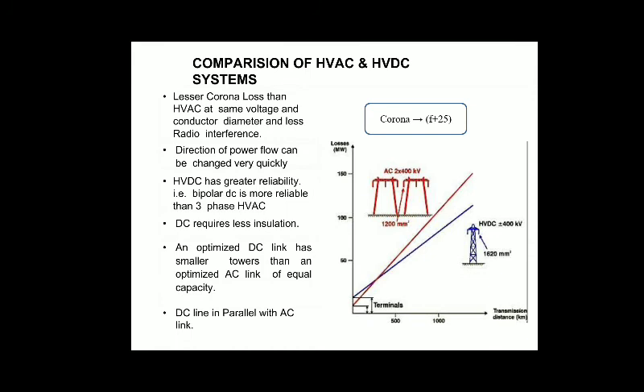In AC, what is corona loss? Corona loss occurs when two conductors are at high voltages and the air between them becomes ionized. Because of this ionization, current passes through the air, producing light and sound — this is called corona loss. The resulting light and sound cause losses in the electrical system. In HVDC, there is corona loss, but it is comparatively low.